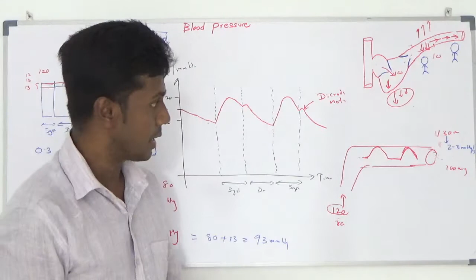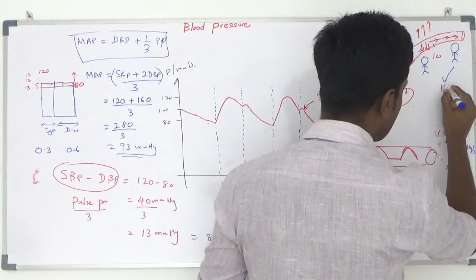Then you keep your stethoscope here. You listen for a sound. We reduce the pressure until that sound appears. How are you going to reduce the pressure? We create a small leak in the sphygmomanometer. Then reduce 2 to 3 millimeter mercury pressure per second. Then you can hear the appearance of that sound. That is called Korotkoff first sound, because it was discovered by Korotkoff.